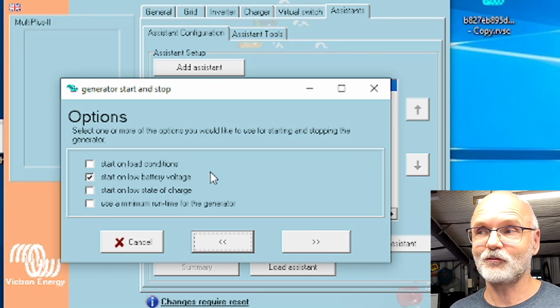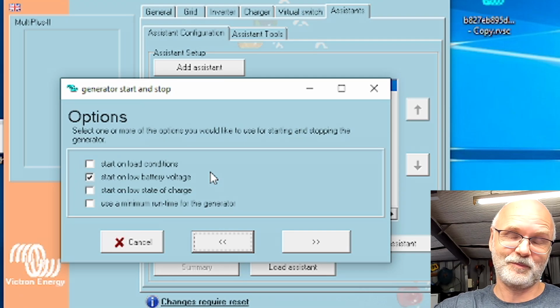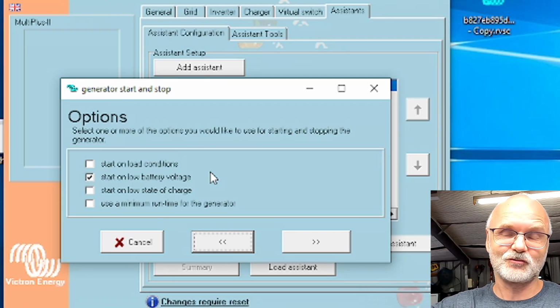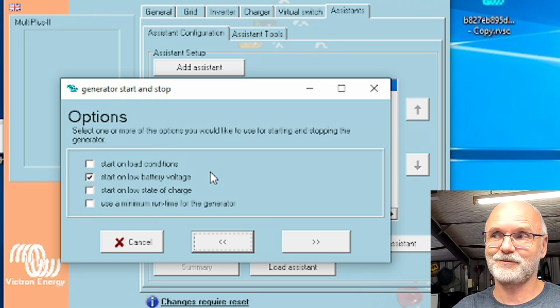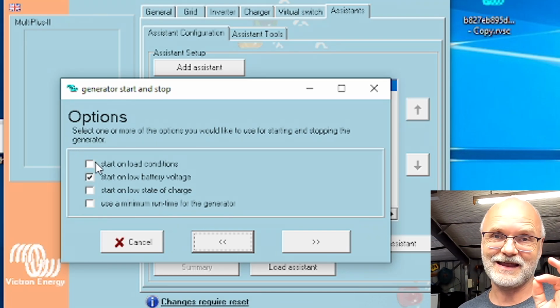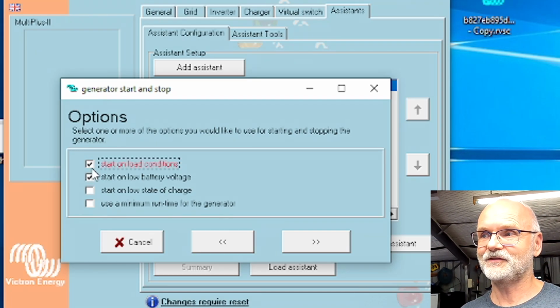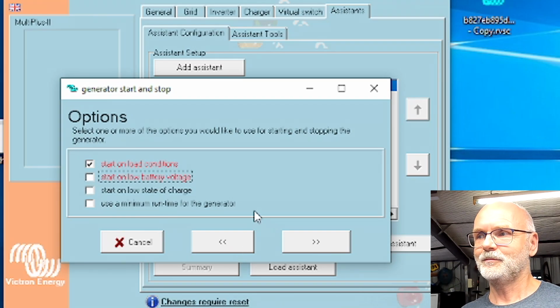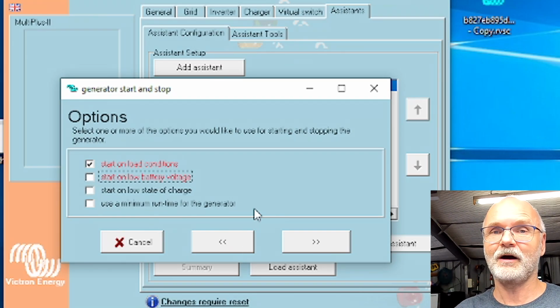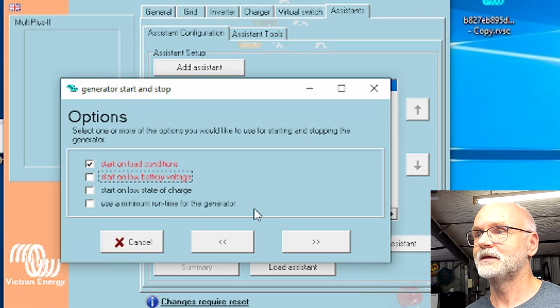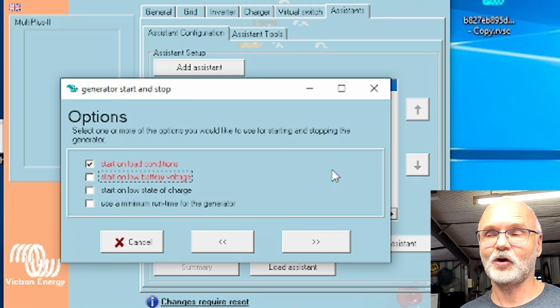If you have a real generator, it would make sense to start it as per battery voltage. If your battery voltage goes low, you want to start the generator to recharge your batteries. This is the main purpose of this whole setup. But in our case, we want to make this load dependent, because we want an additional power input to the system if the Multiplus cannot cope anymore. So we select the first option, start on load conditions.